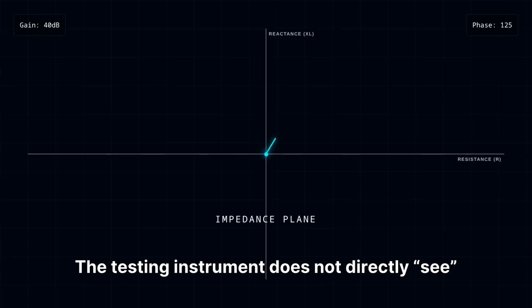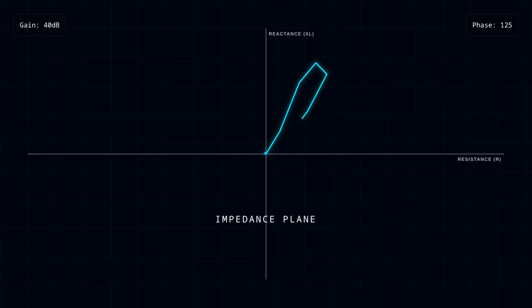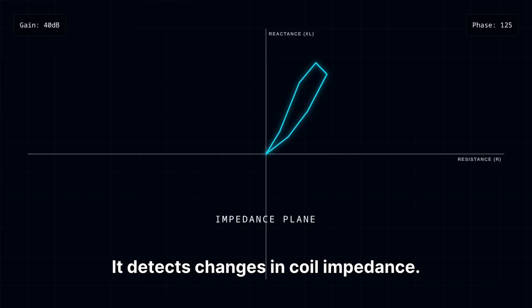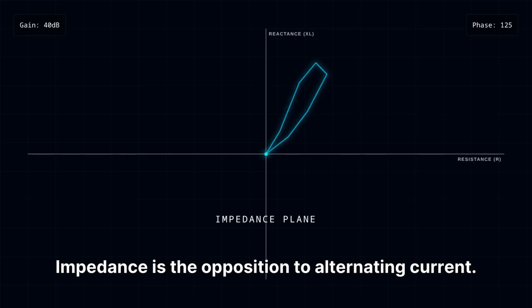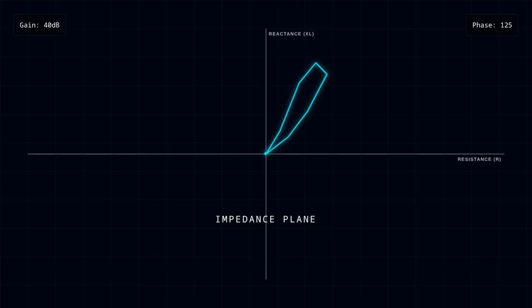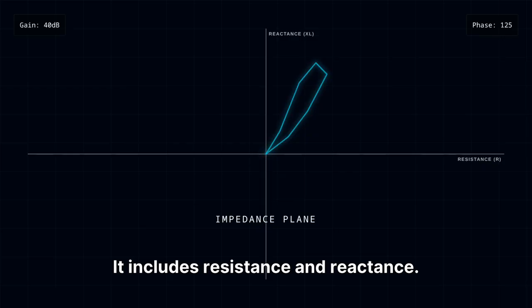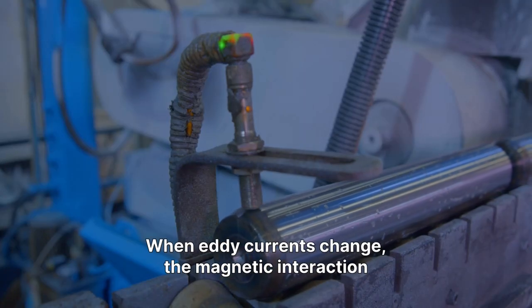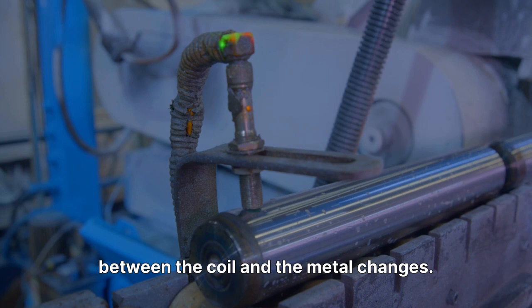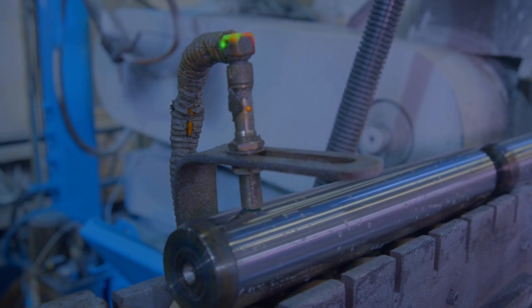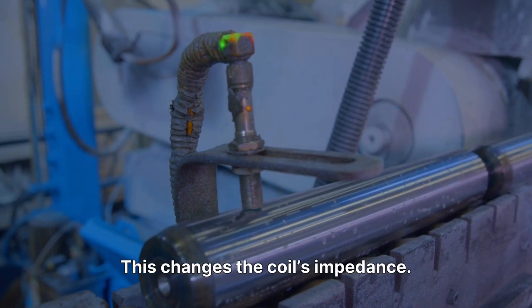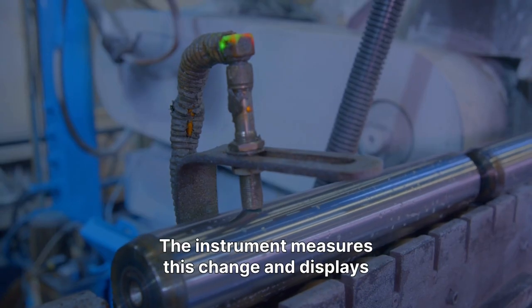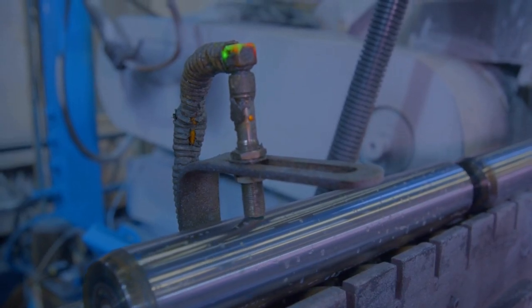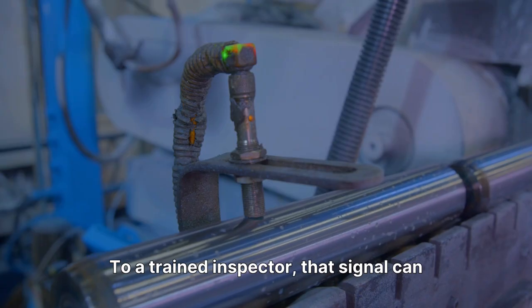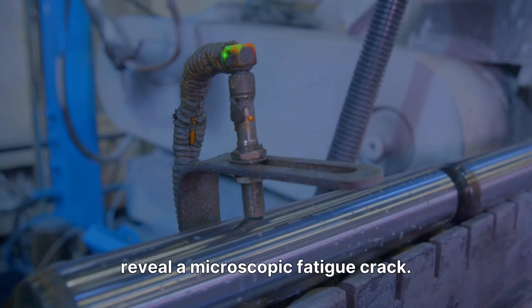The testing instrument does not directly see the crack. It detects changes in coil impedance. Impedance is the opposition to alternating current. It includes resistance and reactance. When eddy currents change, the magnetic interaction between the coil and the metal changes. This changes the coil's impedance. The instrument measures this change and displays it as a signal. To a trained inspector, that signal can reveal a microscopic fatigue crack.